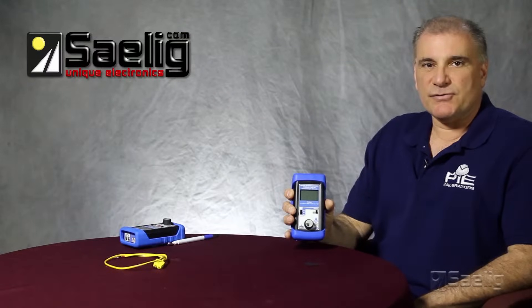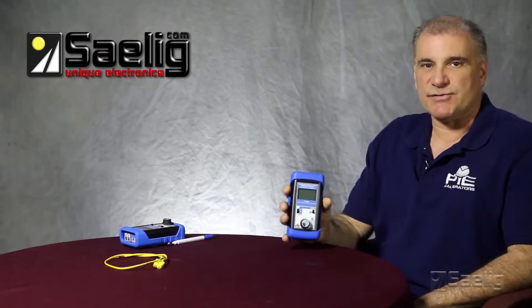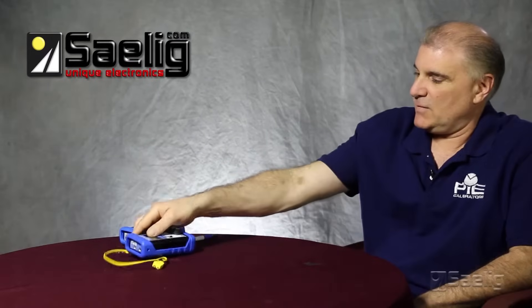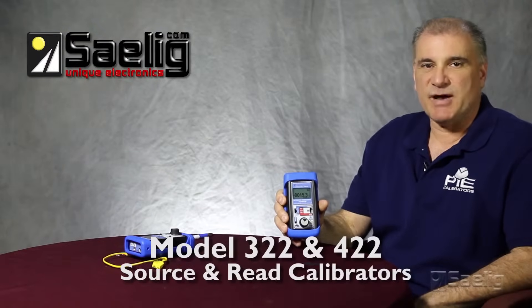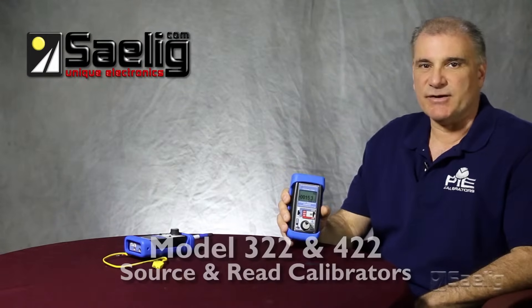They both will simulate the millivolt voltage that corresponds with the thermocouple type and temperature set point. The other two calibrators in this series are the PIE 322 and the PIE 422. These are source and read calibrators.